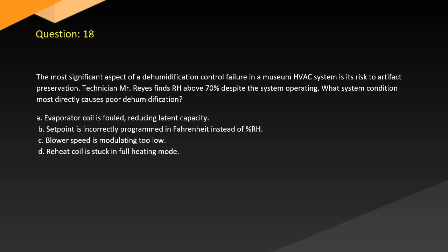Question 18. The most significant aspect of a dehumidification control failure in a museum HVAC system is its risk to artifact preservation. Technician Mr. Reyes finds RH above 70% despite the system operating. What system condition most directly causes poor dehumidification? A. Evaporator coil is fouled, reducing latent capacity. B. Set point is incorrectly programmed in Fahrenheit instead of percent. C. Blower speed is modulating too low. D. Reheat coil is stuck in full heating mode.